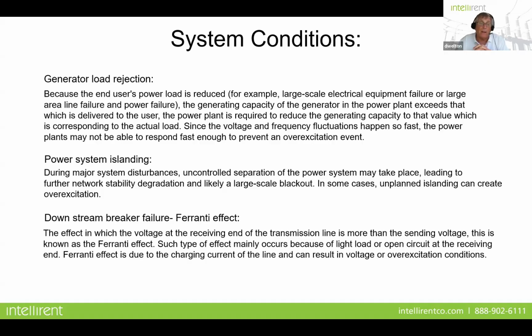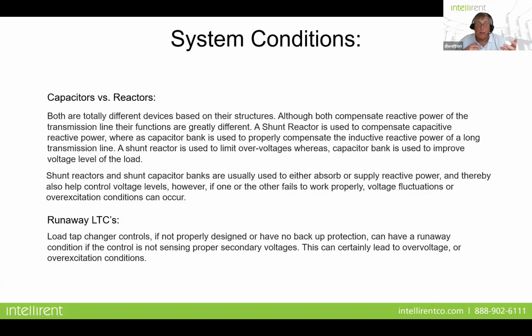Power system islanding. When you have major system disturbances, uncontrolled separation from the power system could take place, and that'll lead to further network instability. Downstream breaker failure creates a Ferranti effect, and that occurs because of light load or an open circuit at the receiving end. So the Ferranti effect is basically due to the charging current in the line that can result in voltage or overexcitation conditions. Capacitors and reactors: when capacitors are off when they should be on, or reactors are on when they should be off, that can also create voltage fluctuations and runaway LTCs.